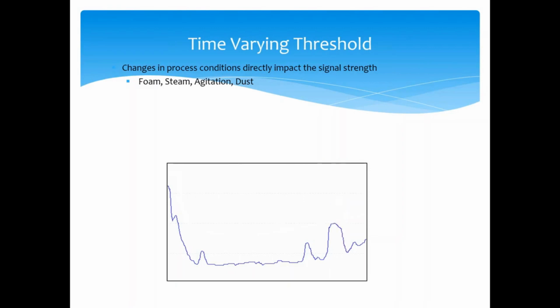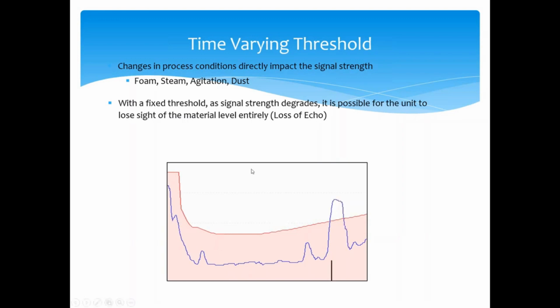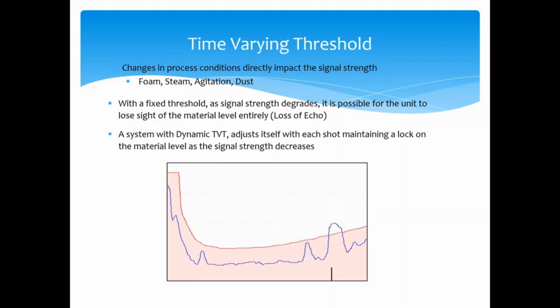So a little bit more on that time varying threshold that we spoke about earlier. Changes in your process condition, things like foam, steam, agitation, dust, whatever the case might be, can cause that signal return or that echo to go from a high amplitude to a low amplitude. So if you had a fixed threshold value, like many non-contact level devices do, when you have that dusty condition or that foamy condition and that signal drops below that red line, your device goes into echo loss, which is an error mode. And in echo loss, you might hold your previous value, fail high, fail low, however you have that instrument set up. The whole goal of the dynamic threshold is, once again, as the amplitude of that signal changes, my threshold changes with it.